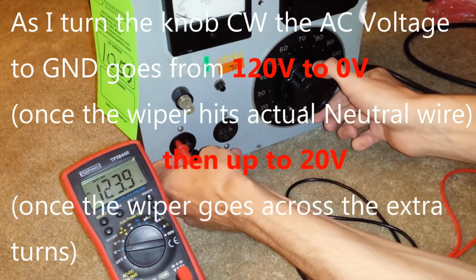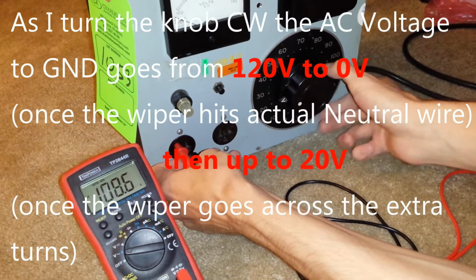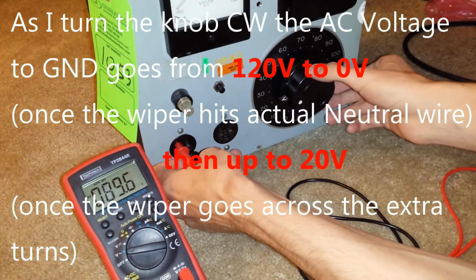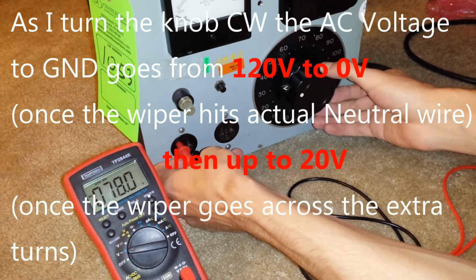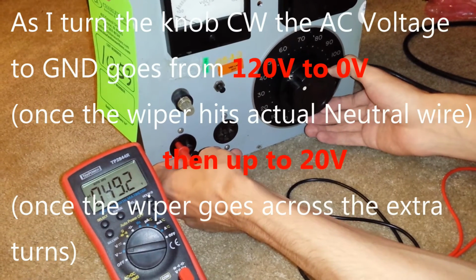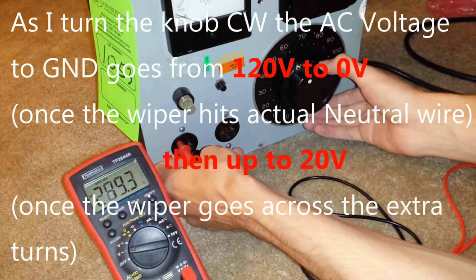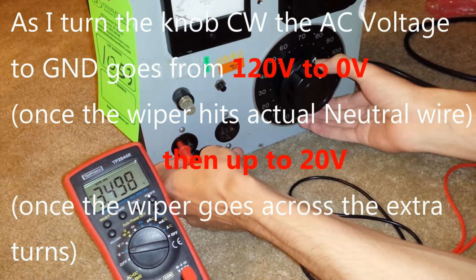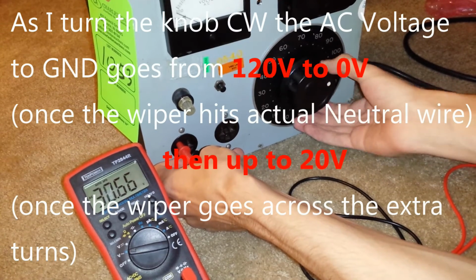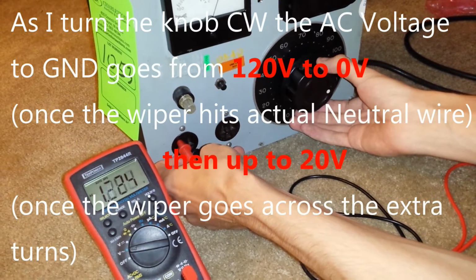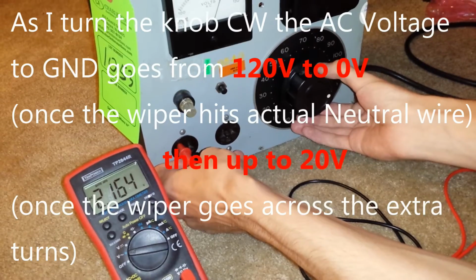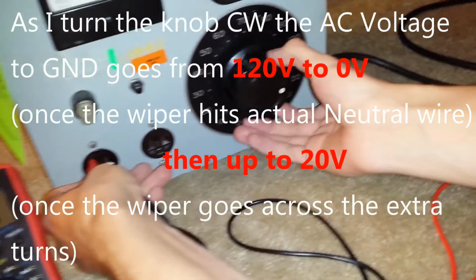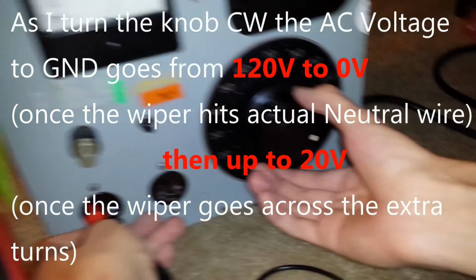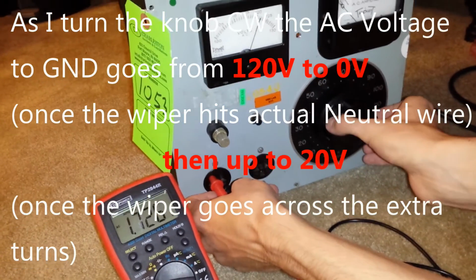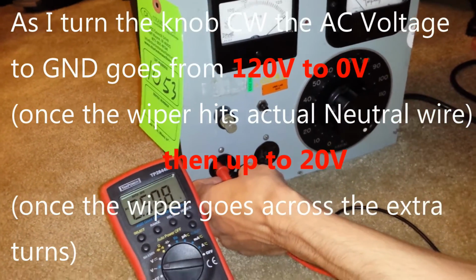As I turn the knob clockwise, the AC voltage to ground starts to drop from 120 down to 0 volts once the wiper actually hits the real line neutral wire. Then it goes up to 20 volts once the wiper goes across the extra turns. You can see right now I'm trying to balance it so that it's at 0 volts, so that the wiper is at the actual neutral wire. And then now I have it cranked so that it's 20 volts because the wiper's across the extra turns.